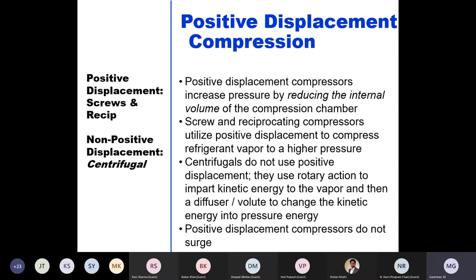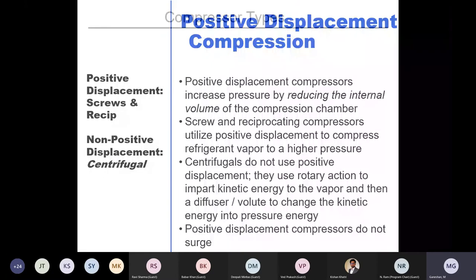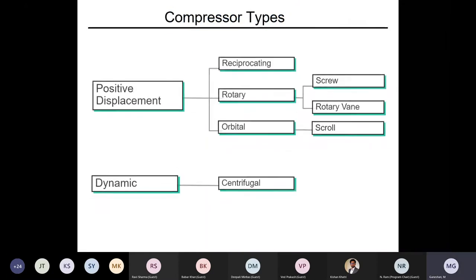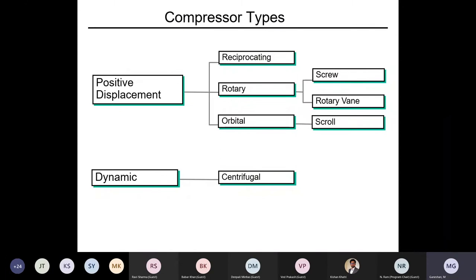We can put these into two types, basically positive displacement and non-positive displacement. Positive displacement is basically screw, reciprocating, scroll, all come into that category. There, in positive displacement, the compressor compresses the refrigerant vapor in a confined space. Whereas in centrifugal, the rotary action is converted into kinetic energy. That's it, only two differences between these two compressor technologies. This is how we classify them. Positive displacement is reciprocating, rotary, orbital, then screw, scroll. The only dynamic one is the centrifugal.